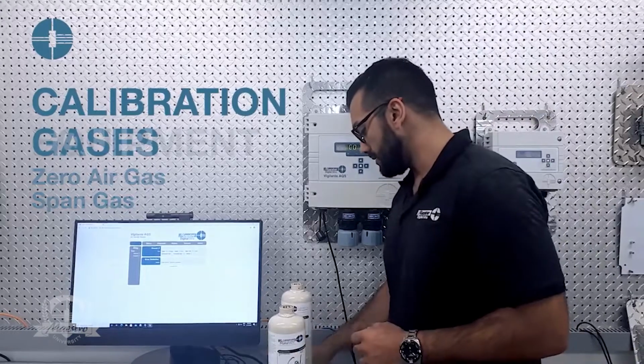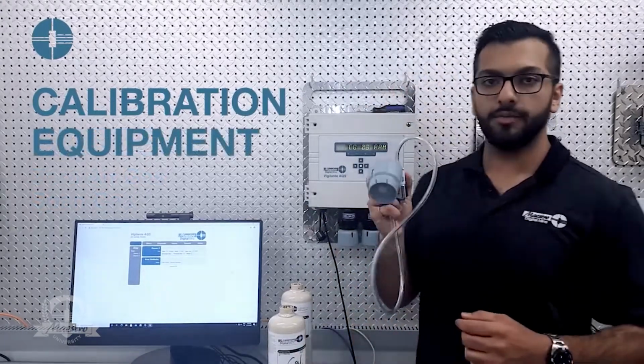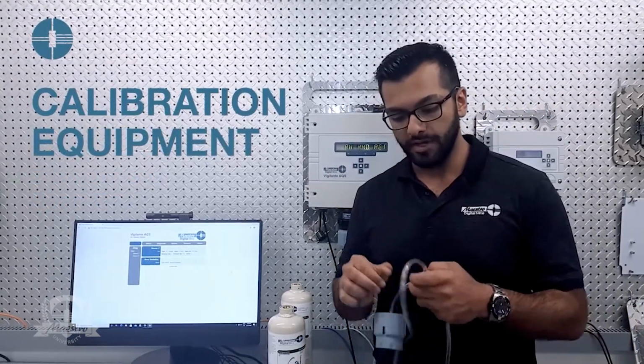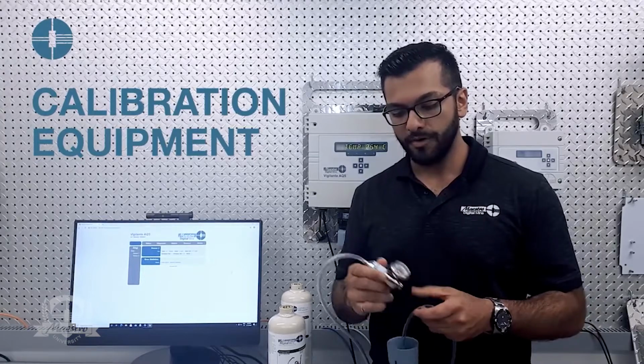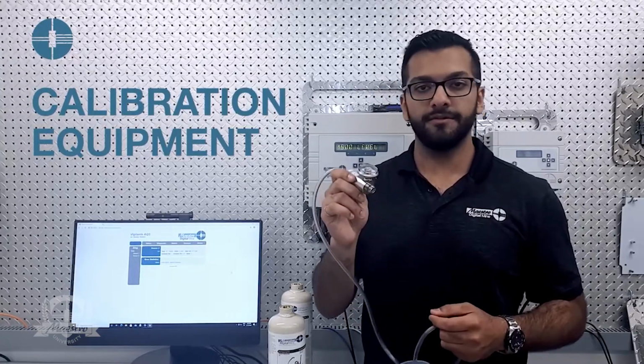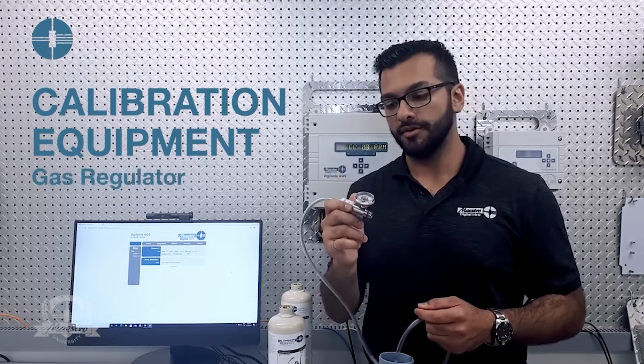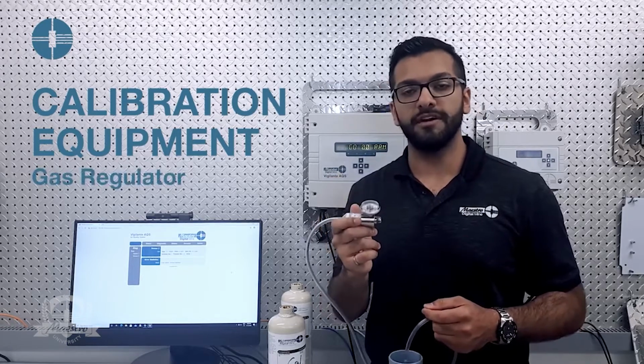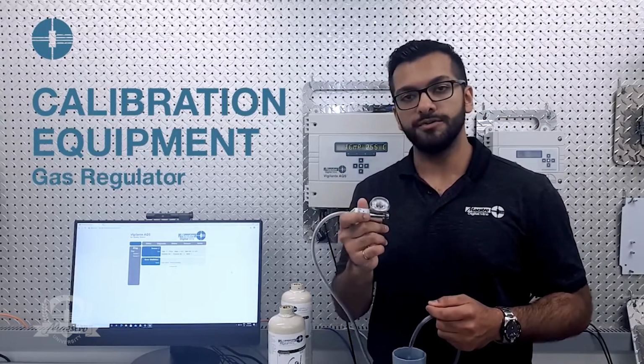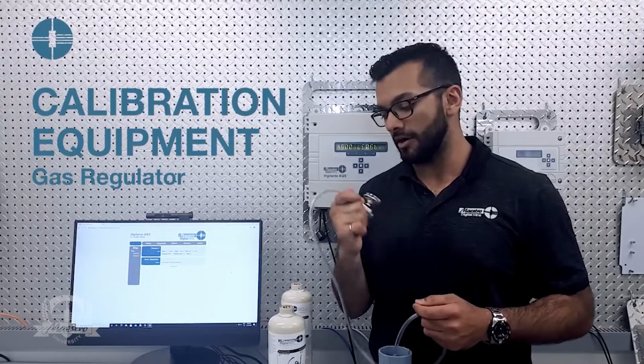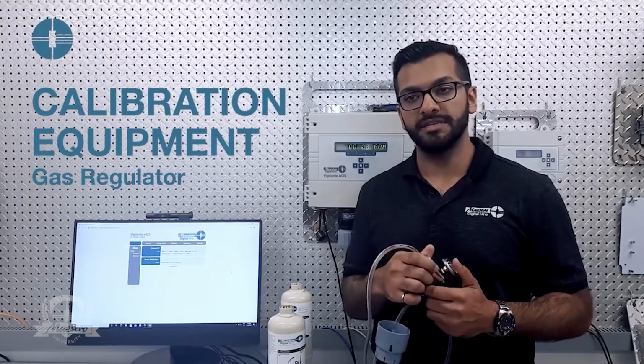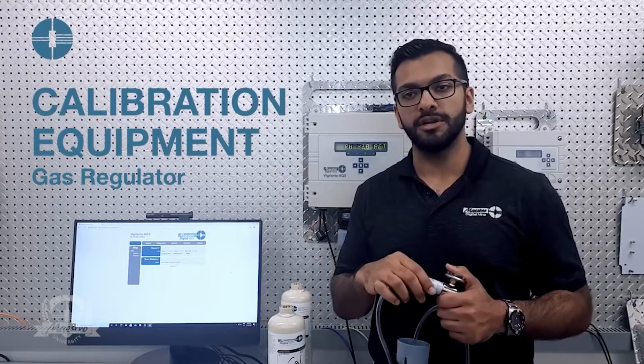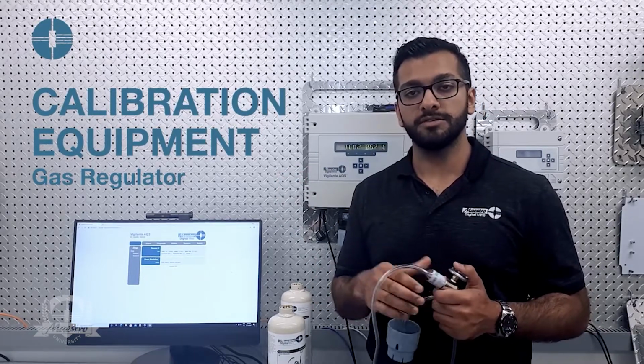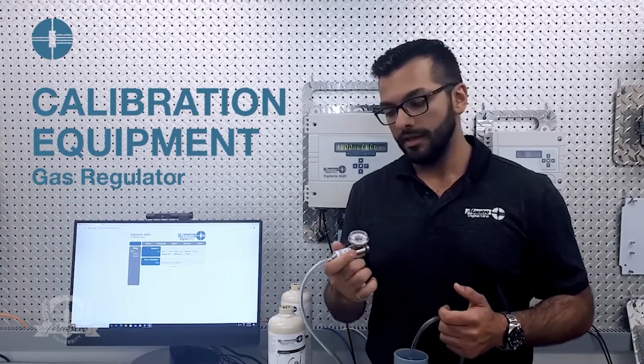After that, the next thing on our checklist is the calibration equipment. For this, we have 3 pieces of equipment, or actually 4. But the first thing is the regulator, which gives a flow of 0.5 liters per minute. It's important to use a regulator with that flow because our gas sensors are calibrated with the same flow. And if you use anything too high, it will actually mess up the calibration based on timing intervals as well.